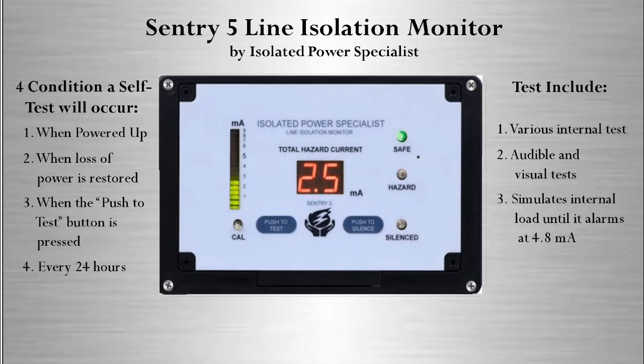The Sentry 5 line isolation monitor is set to alarm at 4.8 milliamps instead of the 5.0 milliamps to ensure that we are within code. Therefore, the line isolation monitor will simulate an internal load until the line isolation monitor reaches 4.8 milliamps. Let's watch the Sentry 5 respond to an increase in leakage.